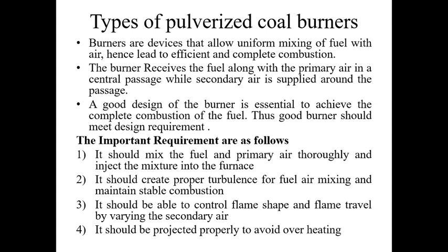are many designs, and the important requirements are that it should mix the fuel and primary air efficiently and thoroughly, and inject the mixture into the furnace. It should create proper turbulence for mixing and maintain stable combustion. It should be able to control the flame shape and flame travel by varying the secondary air. This is the main control. It should be projected properly to avoid overheating. So these are the important requirements.